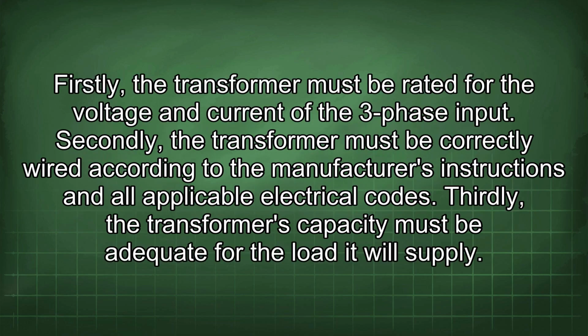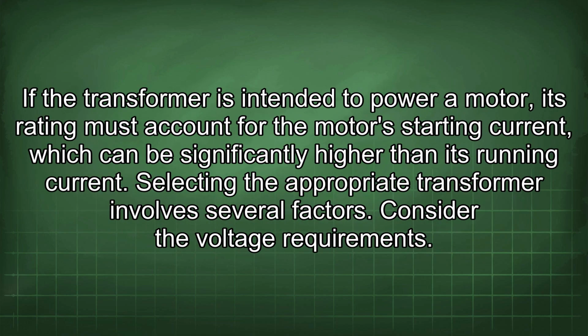Firstly, the transformer must be rated for the voltage and current of the three-phase input. Secondly, the transformer must be correctly wired according to the manufacturer's instructions and all applicable electrical codes. Thirdly, the transformer's capacity must be adequate for the load it will supply. If the transformer is intended to power a motor, its rating must account for the motor's starting current, which can be significantly higher than its running current.